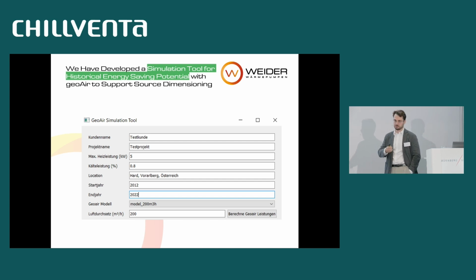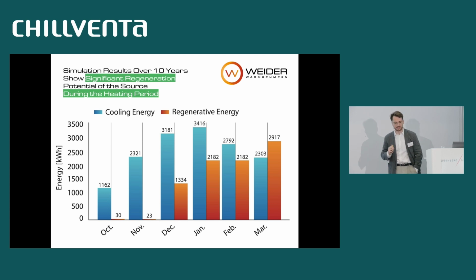And you might argue now, okay, this might work in theory, but this might get complicated in dimensioning, because you have the ventilation system, you have the source and the heat pump, and they all have to work together at the end of the day. This is what led us to developing our own in-house simulation tool to simulate with historical weather data on an hourly basis how much the geoAir actually regenerates at a given location. So you tell it the heating capacity, the cooling capacity, the location, the length, how many years you want to simulate, and the airflow.